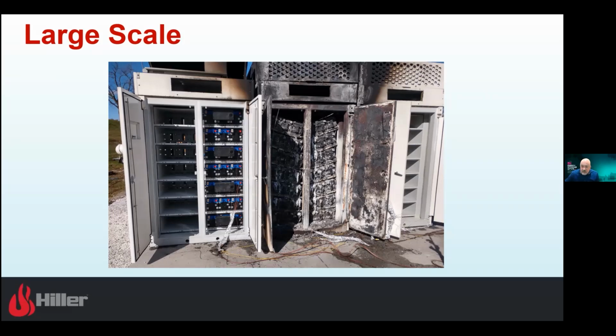Because what happens when these things truly catch fire and are allowed to burn, we get a chimney effect and open up the top of the container automatically. What we end up with is a 3 or 4 hour event. There's no stranded energy, the whole thing burns up. That's a pretty easy situation to put a first responder in. They don't need to engage, they do not need to go out and fight the fire. They just sit back and watch.